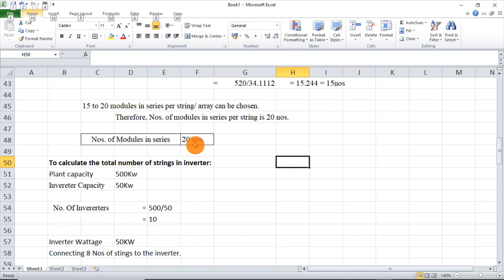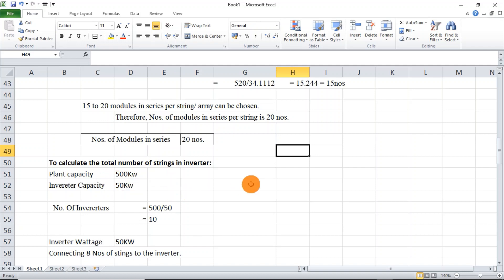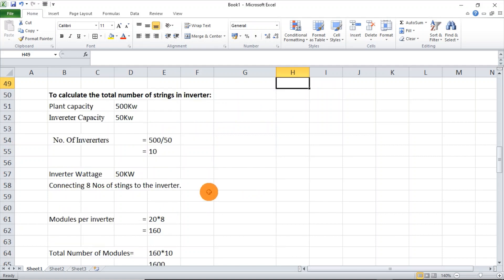I have taken 20 modules to be connected in series with this inverter. Going with a plant capacity of 500 kilowatts and an inverter capacity of 50 kilowatts, the number of inverters to select is 500kW divided by 50kW, which equals 10 inverters.